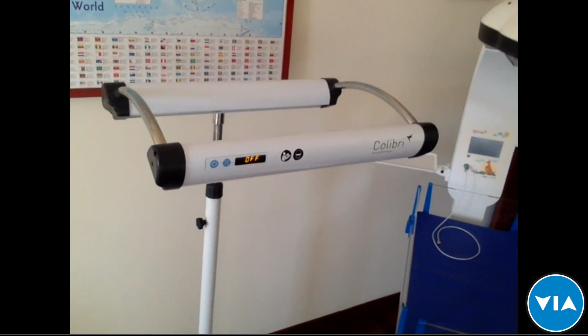So the phototherapy devices, Firefly and Colibri, and the Dolphin, they can have optional battery backup. It's a big battery, about 50 ampere hours, which means it provides about 12 hours battery backup for Colibri, more than 12, probably 14 hours for Firefly, and about 4 to 5 hours for Dolphin CPAP. That's the external unit, something like a UPS for your computer, but a little bit bigger and heavier.